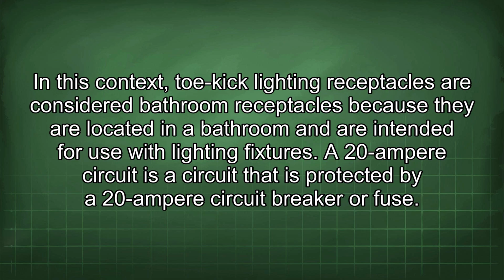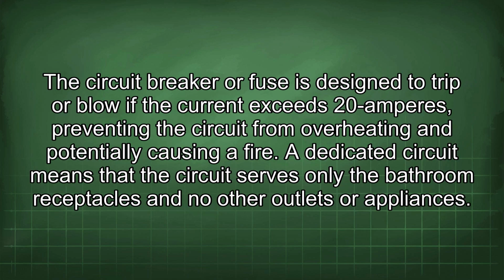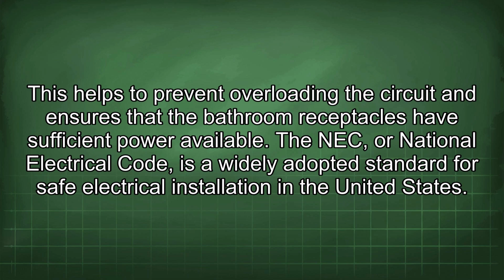A 20 ampere circuit is a circuit that is protected by a 20 ampere circuit breaker or fuse. The circuit breaker or fuse is designed to trip or blow if the current exceeds 20 amperes, preventing the circuit from overheating and potentially causing a fire. A dedicated circuit means that the circuit serves only the bathroom receptacles and no other outlets or appliances. This helps to prevent overloading the circuit and ensures that the bathroom receptacles have sufficient power available.